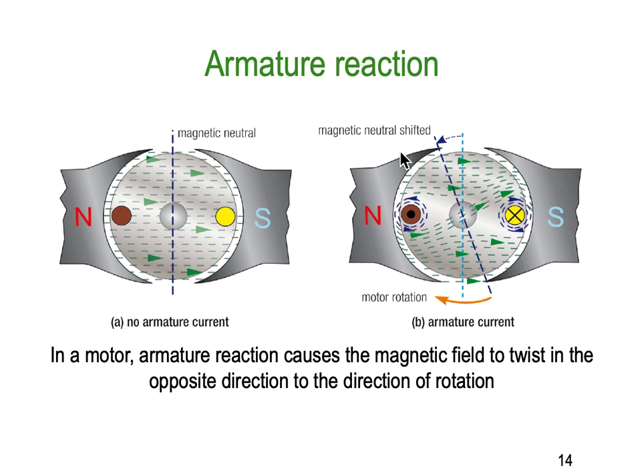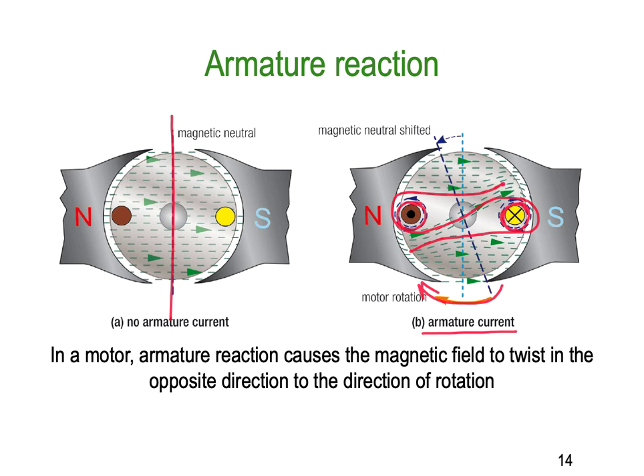Armature reaction — we've spoken about this before particularly with generators, but you also get armature reaction in motors. In a motor, armature reaction causes the magnetic field to twist in the opposite direction to rotation. As the motor rotates clockwise, the armature conductors create their own magnetic fields which oppose the main field, producing this distortion in a figure-eight shape. So instead of the field sitting in the middle, it gets shifted off at a funny angle.